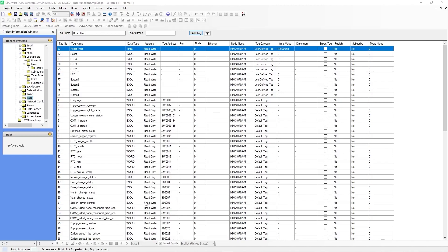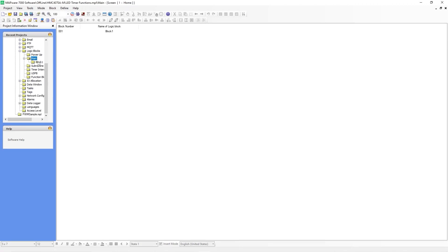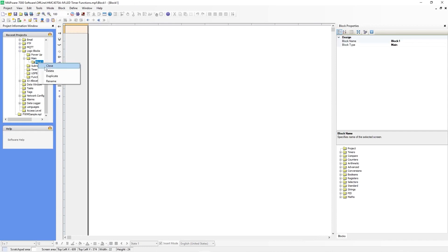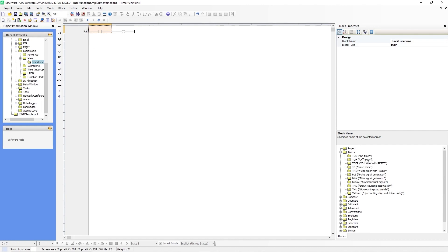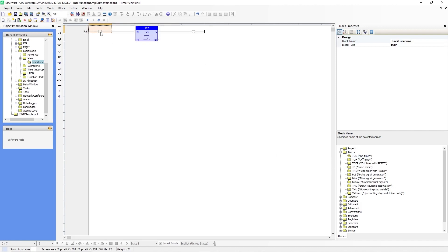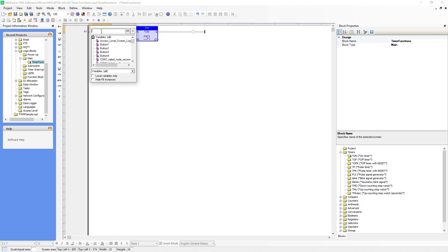Next you will create a logic block. Go to the logic blocks folder, then main. Under block one, we can rename this and call it timer functions. First we'll need to insert a new rung — go to insert new rung. Here we will go over to the right and under the timers folder, we will select TON or on timer and drag it over to rung one. For the input coil, we will use that first tag we created, which was Button 1.